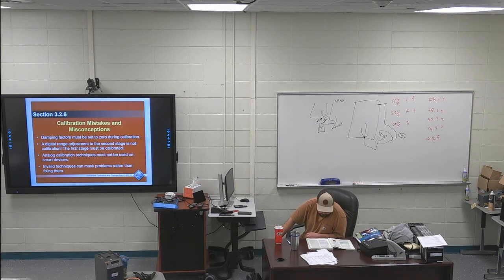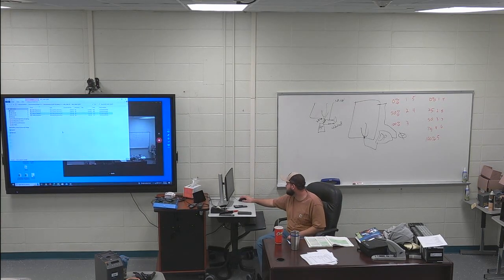Digital range change. I've got the last sentence of that bullet point highlighted, all the way at the bottom left of 23. Calibration always requires a traceable external device, such as a multifunction calibrator, to supply and monitor an input signal to the device under calibration. They go through the zero and span adjustment, loop current adjustment. I don't have anything in those. That's all my highlights for section 3. But good. Going on to our last section.